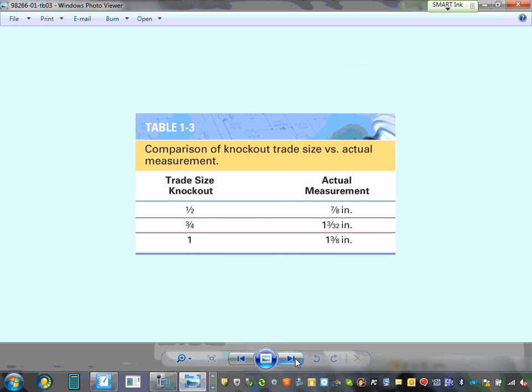This is from the NEC code book. Actual measurement - and you guys who came from electrician backgrounds are familiar with this. When you say half an inch EMT conduit, that's not the actual size of the EMT conduit, that's a trade name - the actual size is a little bit bigger. So if you take trade size half an inch EMT, half an inch rigid, and half an inch PVC, you'll find the internal diameter of these conduits is slightly different. But we call them all half an inch as a trade name. Just be aware of that. Same thing for knockouts.